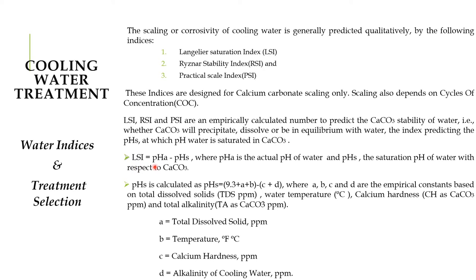Langelier Saturation Index is equal to pH actual minus pH saturated, where pH is the actual pH of the water and pHs is the saturation pH of water with respect to calcium carbonate. pHs is calculated as: pHs = (9.3 + A + B) − (C + D), where A, B, C, and D are empirical constants.